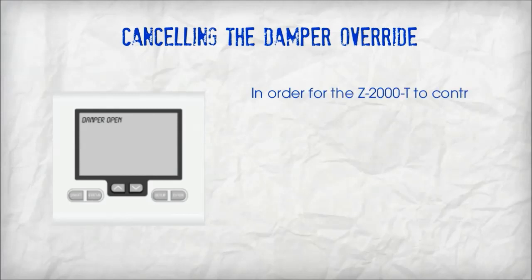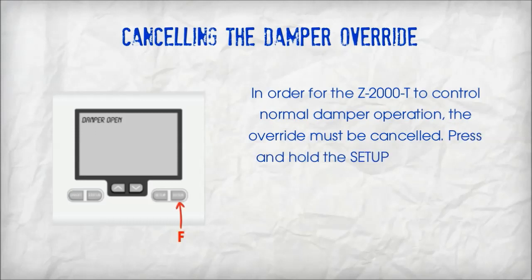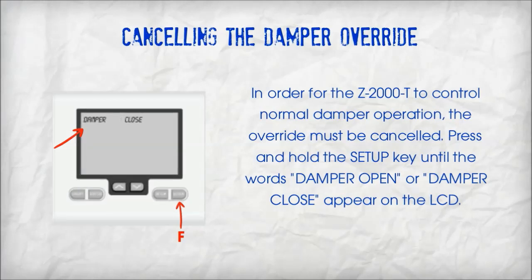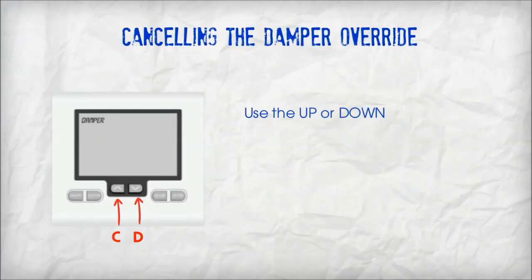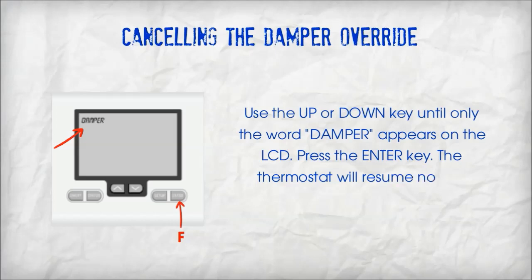In order for the Z2000T to control normal damper operation, the override must be cancelled. Press and hold the setup key until the word 'damper open' or 'damper close' appears on the LCD. Use the up or down key until only the word 'damper' appears on the LCD, then press the enter key. The thermostat will resume normal operation.